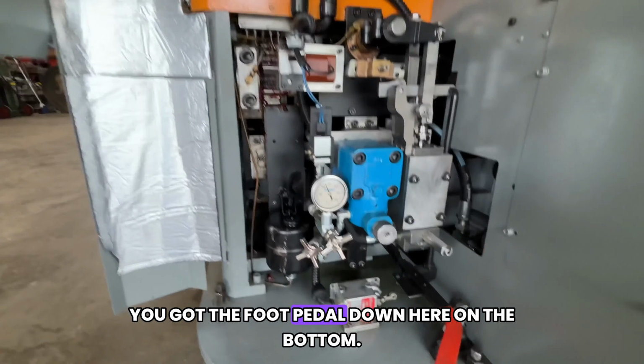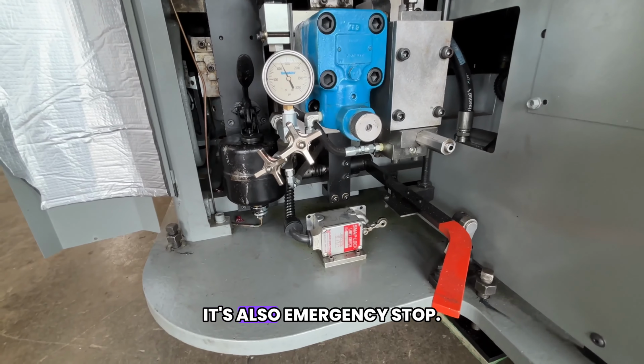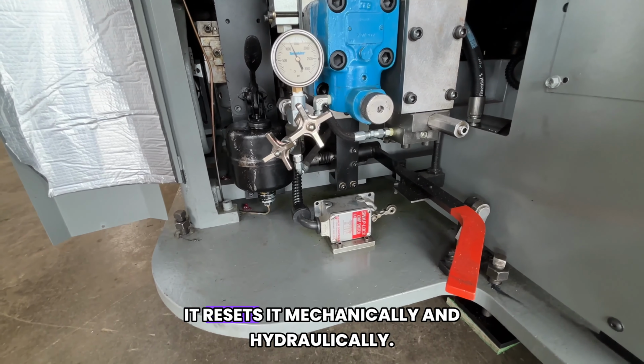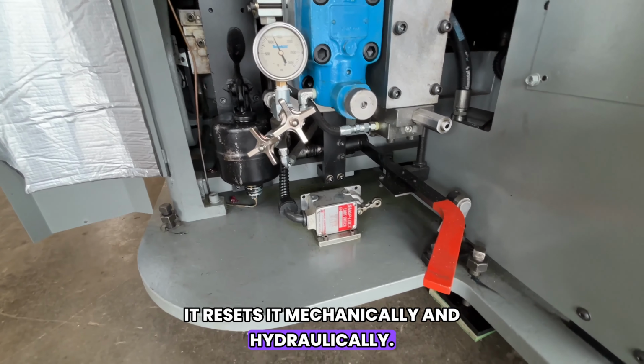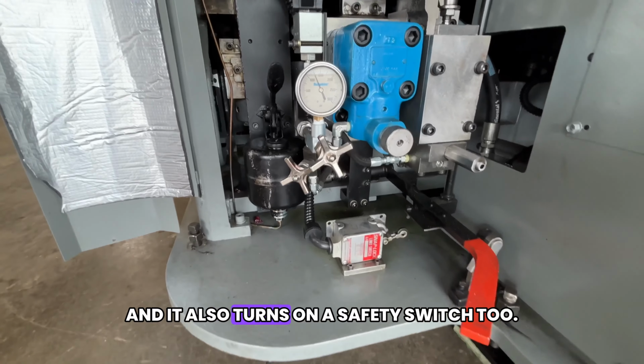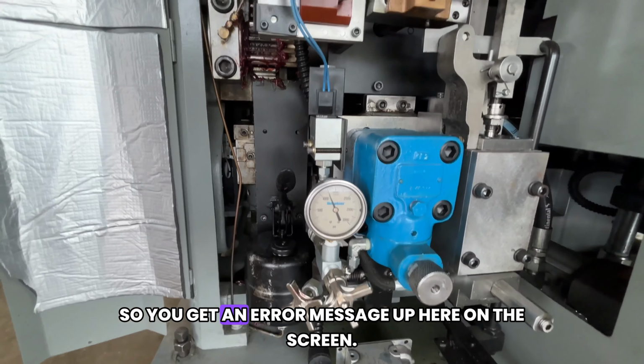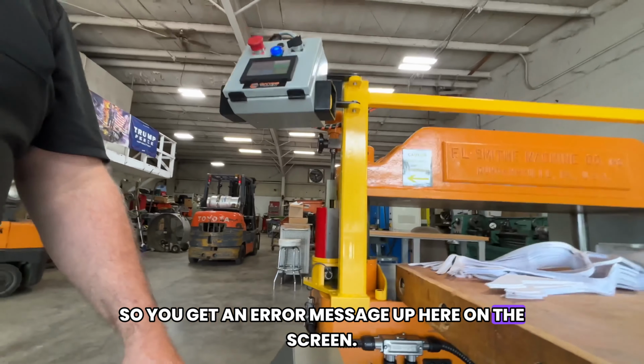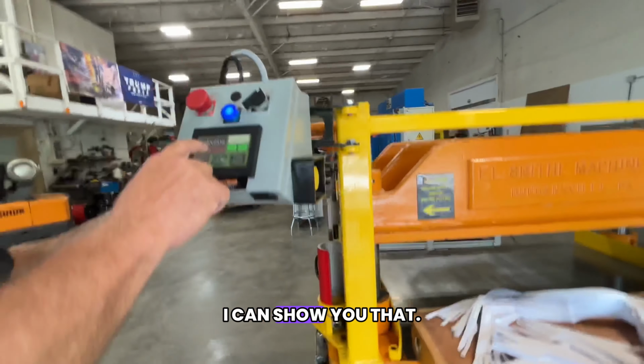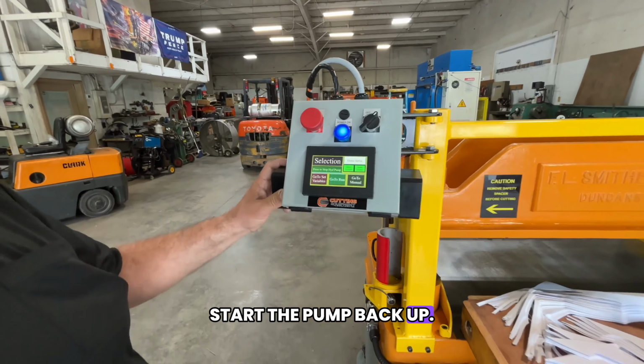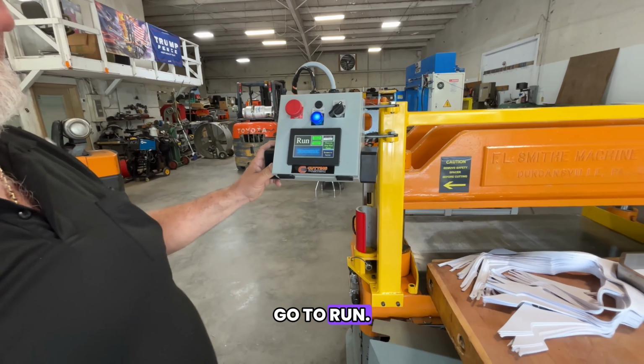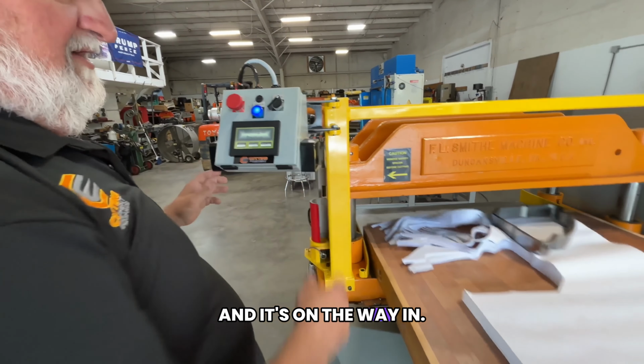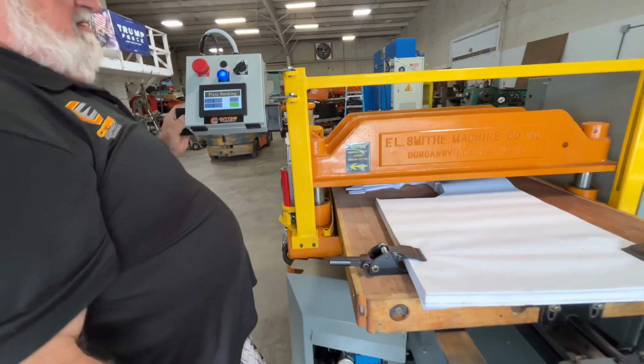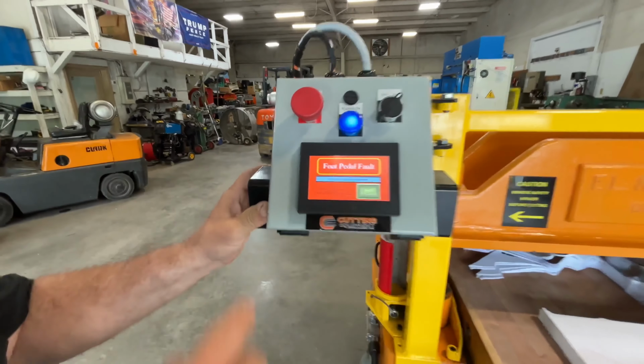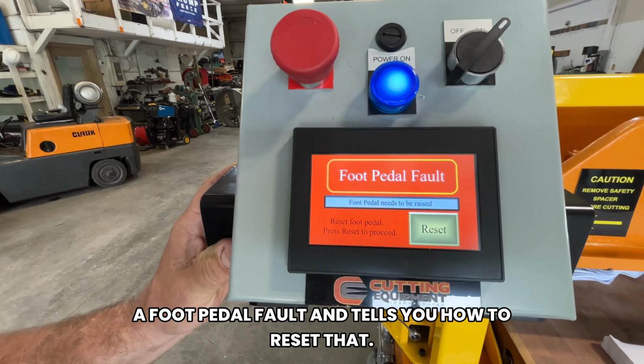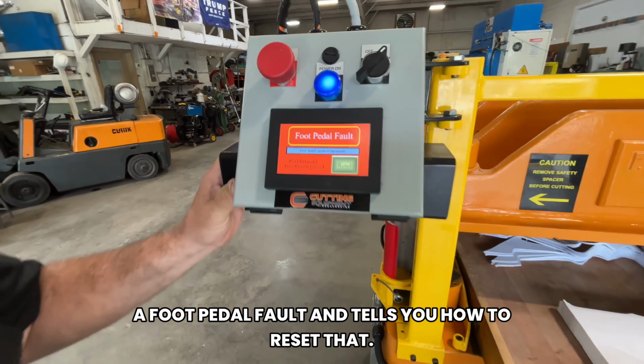You got the foot pedal down here on the bottom. It's also an emergency stop. It resets it mechanically and hydraulically, and it also turns on a safety switch, so you get an error message up here on the screen. I can show you that. Start the pump back up, go to run, and if it's on the way in, it'll say foot pedal fault and tells you how to reset that.